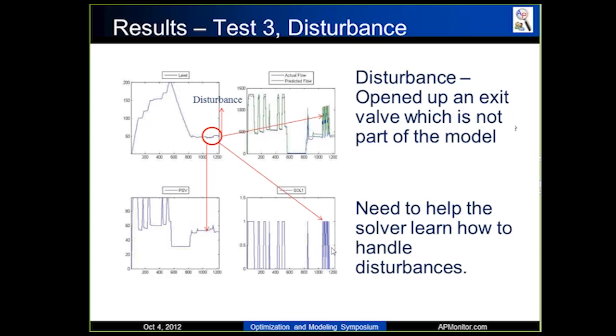So when there's a disturbance that's very large in the model, something that it's totally not accounting for, the model breaks down, and the model predictive control solving just doesn't work very well, and all of a sudden the solenoid valve is on and off. So if there's small disturbances in the model, I noticed that it's able to handle it. But if there's large disturbances in the model, meaning you change things where the model doesn't really accurately capture what's going on, then you're going to have very large issues with your responses.